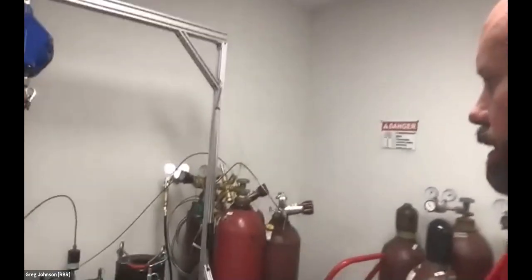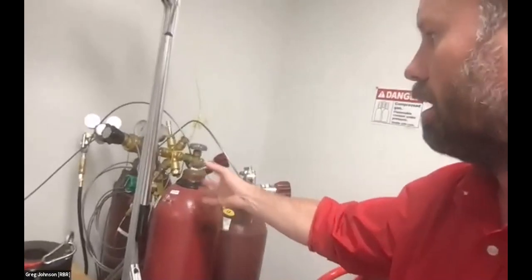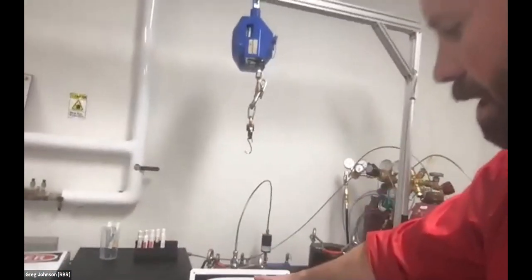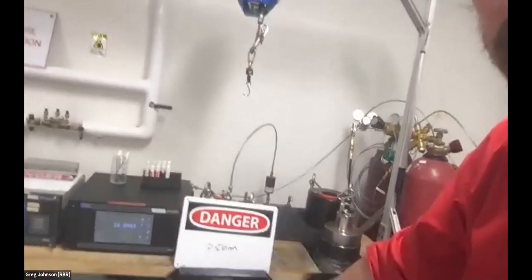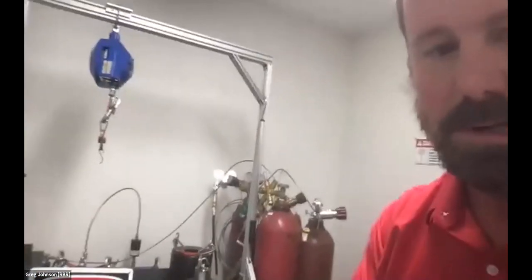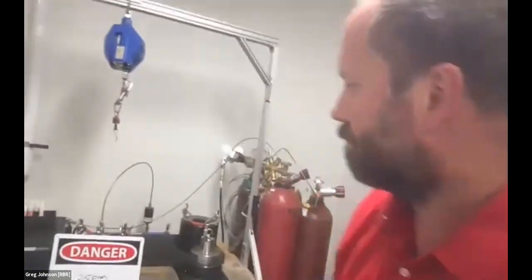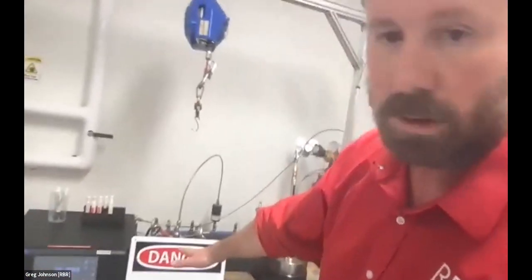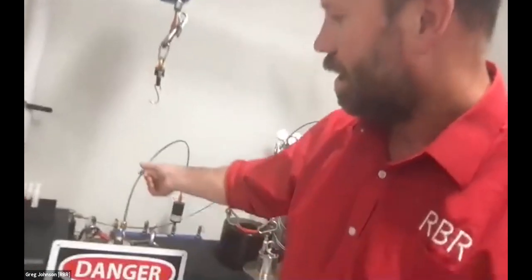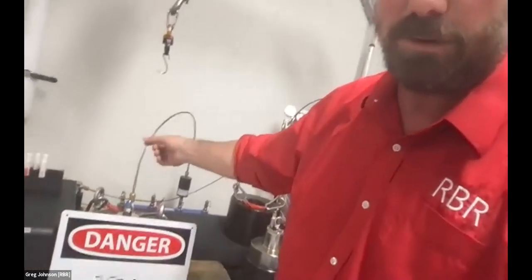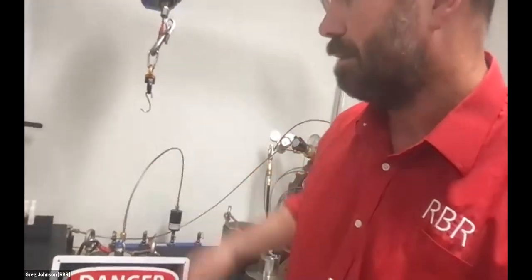The pressure is applied pneumatically through a gas, not through liquid hydraulically. And so these nitrogen tanks that are here in the corner are being driven by these pressure controllers. We don't actually fill the tank with gas because we don't want to store a lot of compressed energy. That's called building a bomb, and we don't like to do that inside the lab. Instead, we fill the tank with water, put the instrument inside, and then pressurize only the very top of the fluid using the gas-filled pipes.